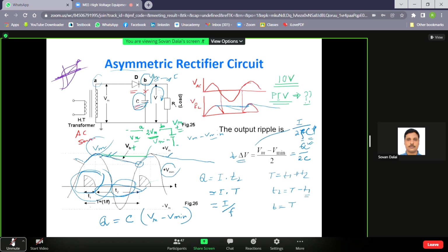And mind that here the diode is designed, say if this VM is 100 kV, so the diode should be designed for 200 kilovolt. Okay, so just for your knowledge, the peak inverse voltage of a silicon diode can go up to maximum 2 to 3 kilovolt. That is peak inverse voltage. So a large number of diodes should be connected in series to achieve a high peak inverse voltage. Okay, this is one of the problems associated with this. We will discuss these things later at the end of this topic, how you select the diode for this rectification scheme.